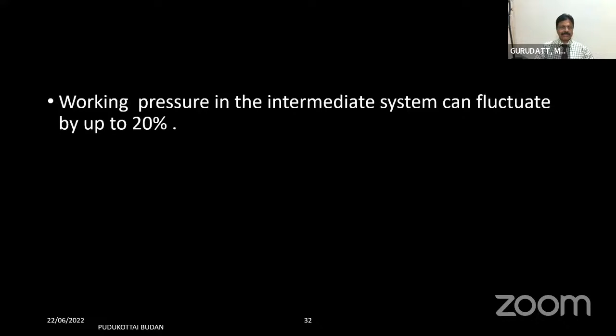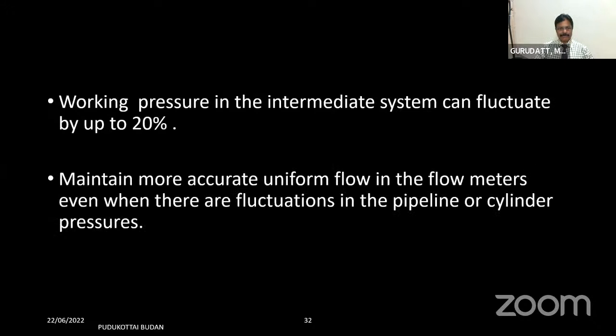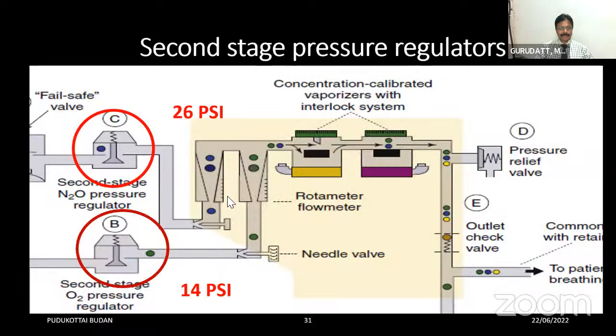So whenever there can be a fluctuation, even up to 20%, the flow in the flow meters will not alter because of the second stage pressure regulators that are there in the GE machines. Another important thing is that because of that, they maintain an accurate flow. And the second, most important thing I just showed you here: the pressure of nitrous oxide is slightly higher. It is almost double the oxygen pressure. So that means they have a 1:2 ratio here.